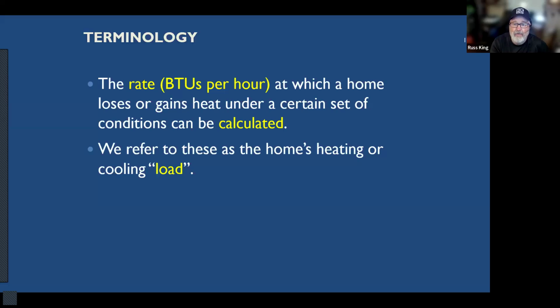So the rate at which a home loses or gains heat because of outdoor conditions being different than the inside conditions, we can calculate that. We can say it's a certain temperature outside, we want it to stay a certain temperature inside, and we've got this house that's separating those two. We can calculate how many BTUs are going to come in and go out. We call that a heating or cooling load, a load calculation. So that's what we mean when we talk about load calculations. Now you may run into other load calculations such as an electrical load calculation, but that's different. We're talking about BTUs, heating and cooling load calculations.